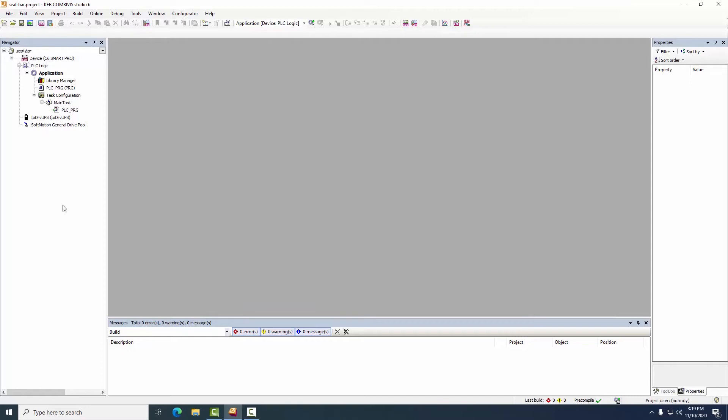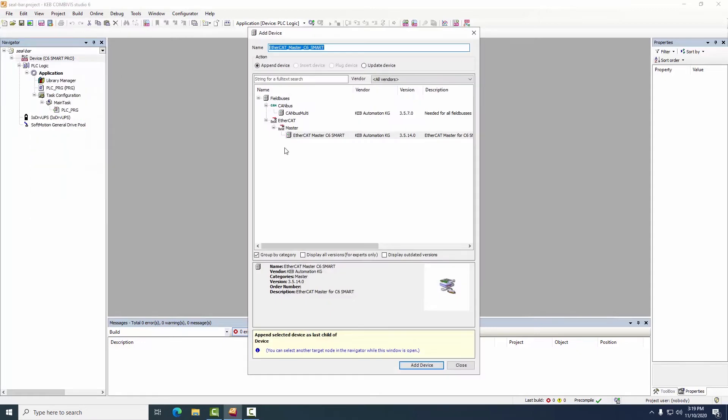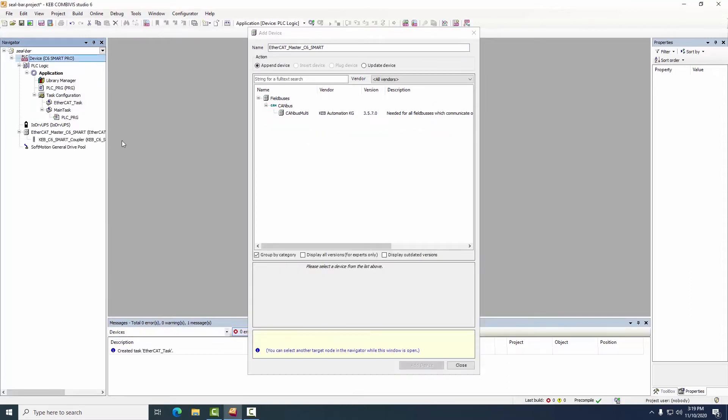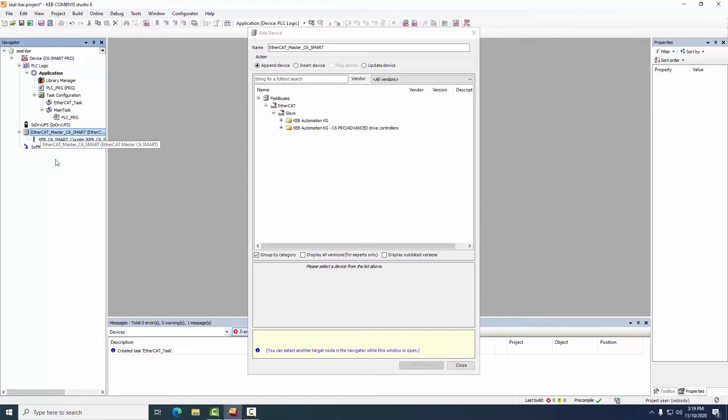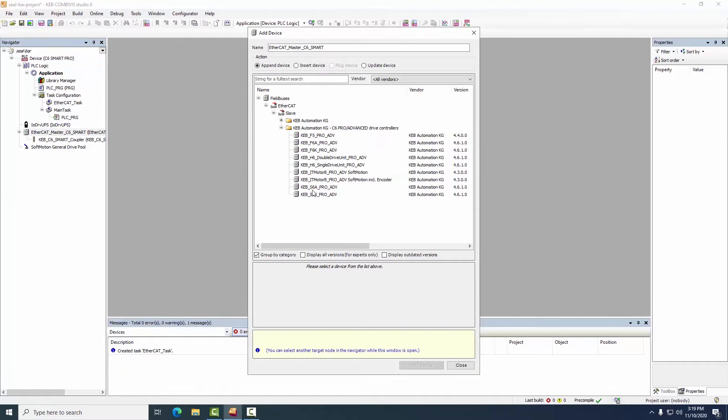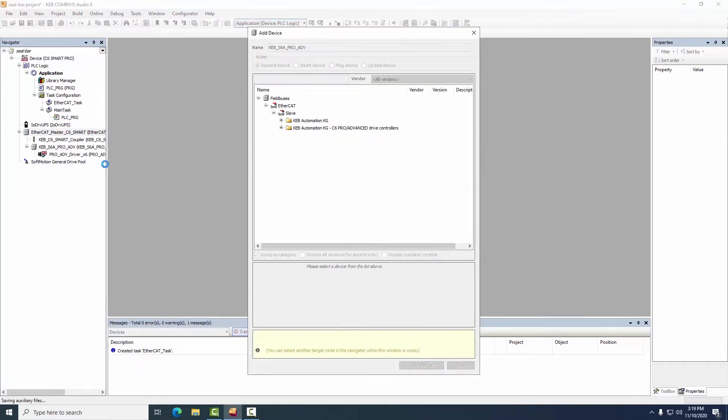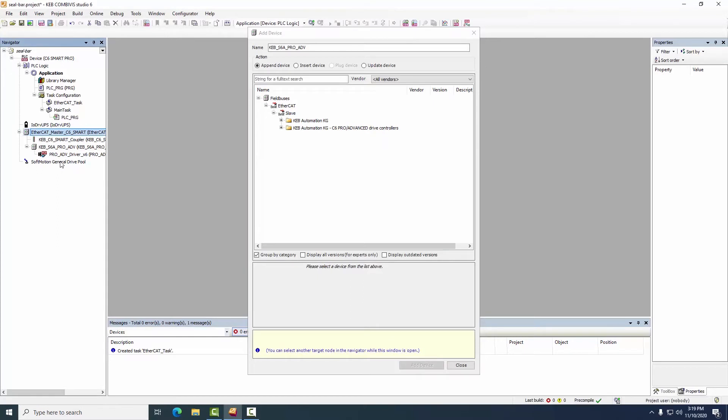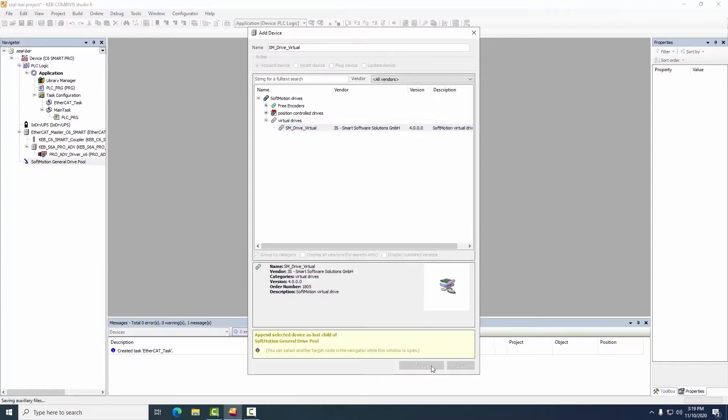The software tool creates a shell program on the left and we need to add a few items to it. For example we will need to add the EtherCAT master itself and when I do that it already knows that we are using the C6 smart product which happens to have a side EtherCAT port for remote IO so that coupler is added automatically. I'm going to add our KEB servo drive which will be used to run the seal bar and for the infeed conveyor for this demonstration I'm going to use a virtual drive otherwise known as a fake drive.